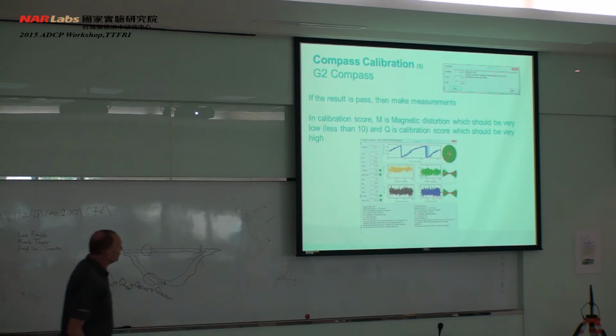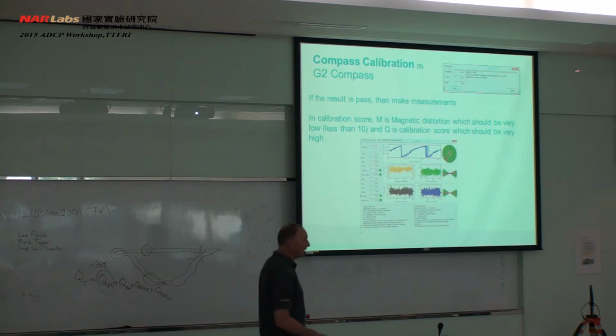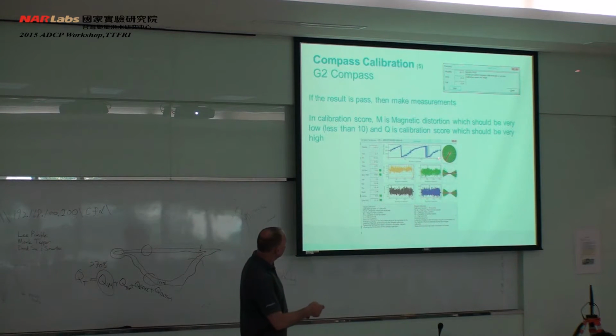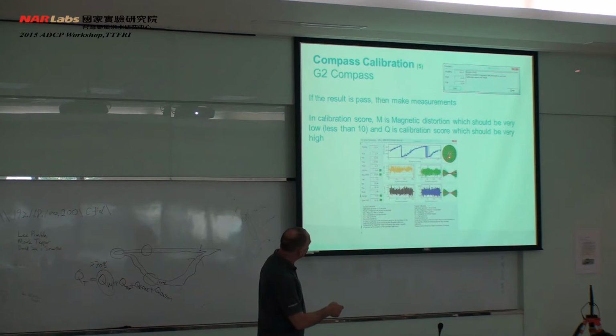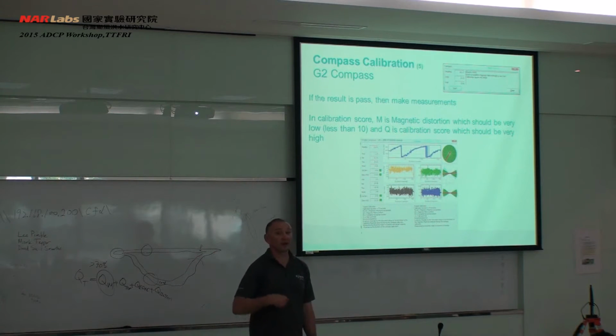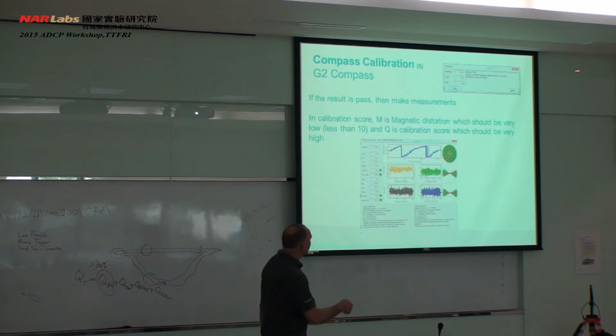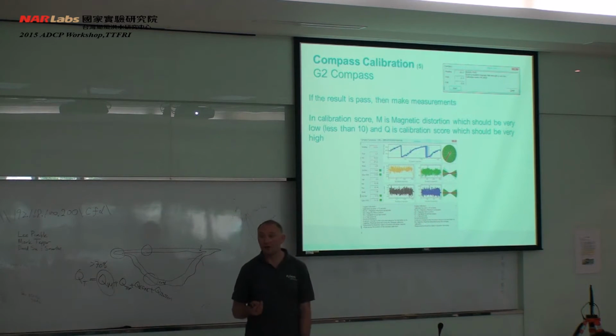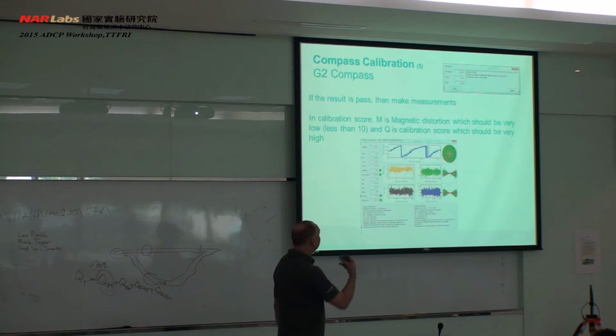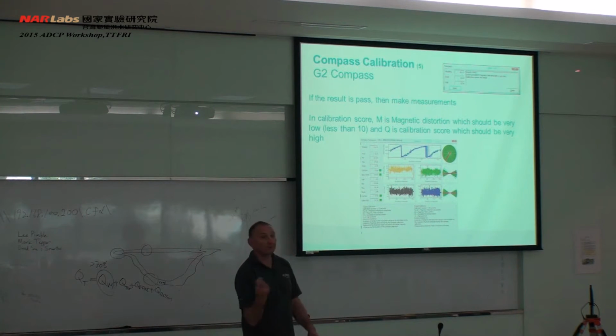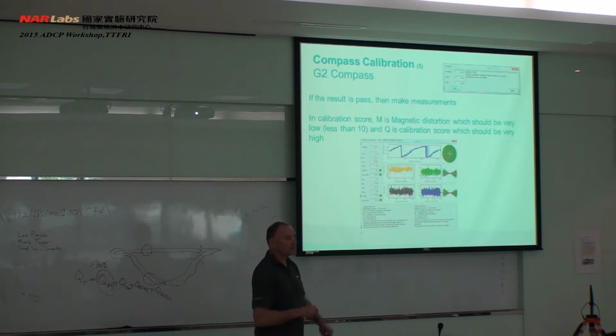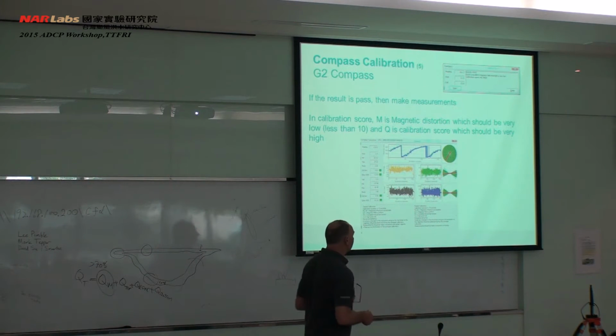This screenshot here actually shows the older compass, so very slightly different here. We have this circle at the top that starts off clear with white, and as we do our rotation, it starts to infill with green. The perfect situation is to have it fully infilled with green. If you had sort of blues and whites in there, then you've got a slightly weak calibration.